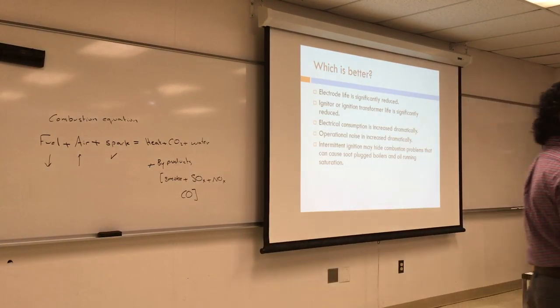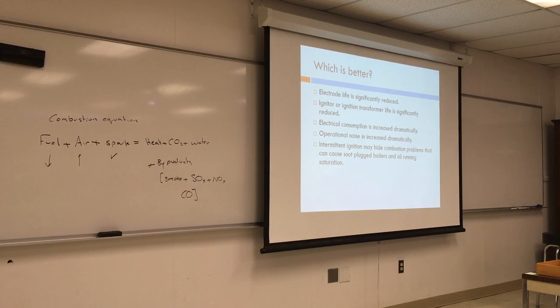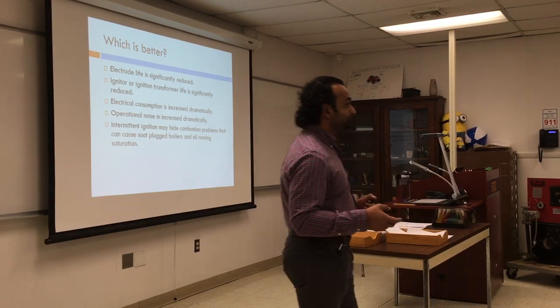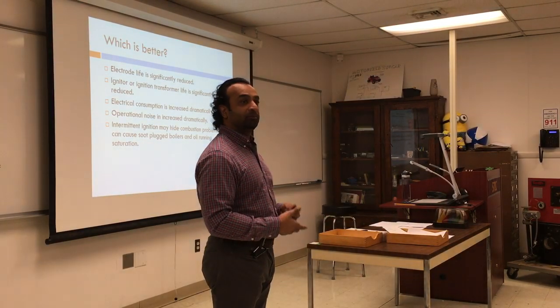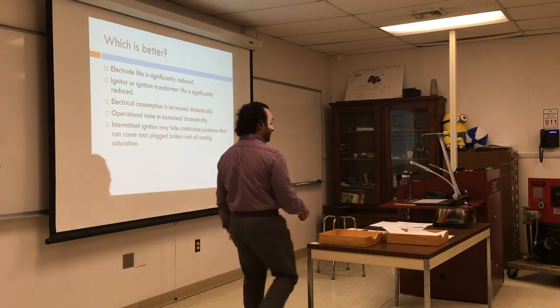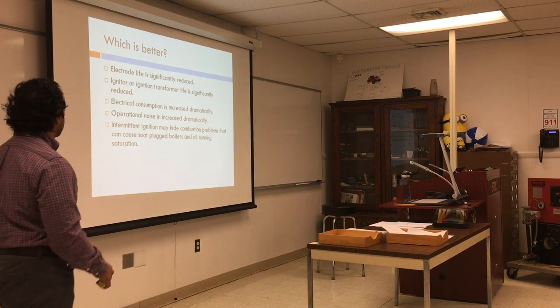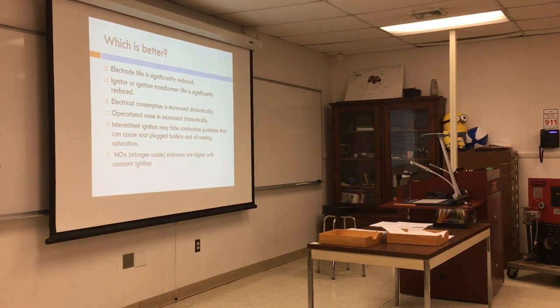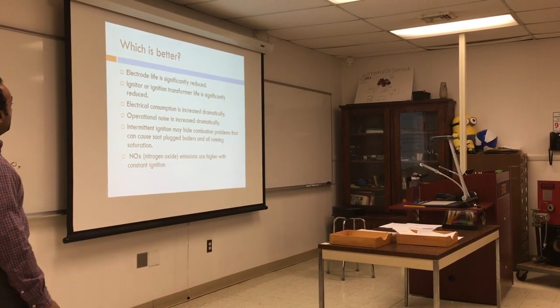So if your car is, again, I always go back to the car example. If your car is burning oil or having incomplete combustion, the car will still run because at each cycle you will have a spark. And it will always burn, but again, you'll have some smoke coming out, but it will still run. Same thing here, it will still run, but it will be incomplete combustion. Nitrogen oxide emissions are higher with constant ignition, and again, Massachusetts is a low NOx state. They don't want you to have nitrogen oxide. The X here stands for any number of oxygen. It could be NO2, NO3, NO1. So any kind of nitrogen oxide is not preferable, or also sulfur oxide.